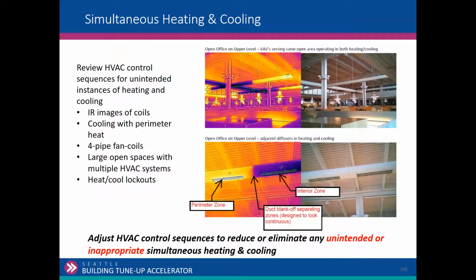This is a big open office area here, and the architect wanted the ducting to all look like it was one piece. So there's actually multiple zones, but it looks like one duct. There's actually a blank off panel here. But what you're seeing is the perimeter zone. Is it in heating or cooling? It's in heating. This is the core zone. Is it in heating or cooling? It's in cooling. So this is a situation in an open office where we have simultaneous heating and cooling.